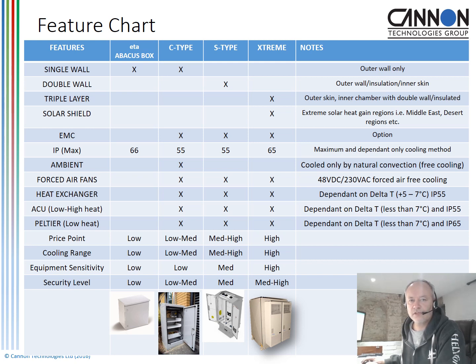And then the next highest range product is what we call extreme. This is used in projects for defense or communication applications where it's in areas, regions like the Middle East or Africa, etc., where you've got much higher temperatures. What we have is a triple layered construction, and basically an outer solar shield. The outer solar shield further reduces the amount of heat that's pushed into the cabinet because of solar heat gain. The triple layer also provides an outer layer which allows air to move around the inner chamber, which is double insulated.